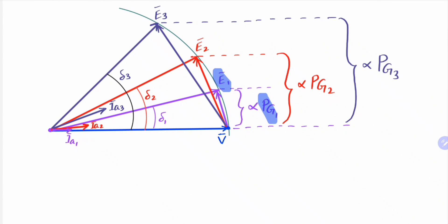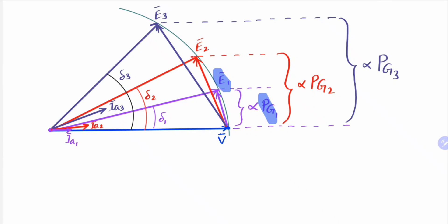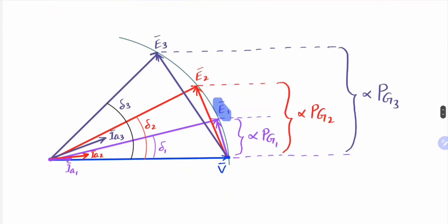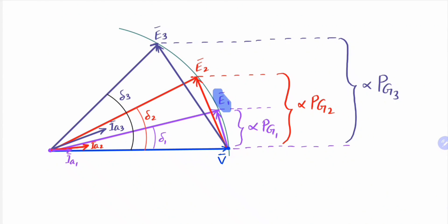For condition 1, just after synchronization when power supplied was pg1, the armature current ia1 is very small, and V + j·ia1·xs gives E as the phasor e1. For case 2, when active power has increased to pg2, the armature current has increased to ia2, and the emf phasor e2 = V + j·ia2·xs (armature resistance ra is ignored). The vertical projection of e2 is proportional to pg2. For the third case, when the governor set point is increased further and power contribution is pg3, this equals e3·sin(δ3), where δ3 is the power angle corresponding to pg3.